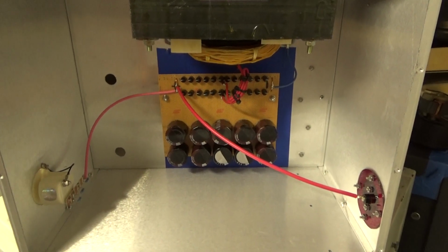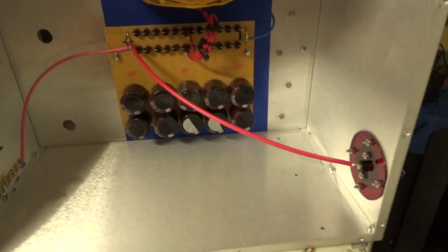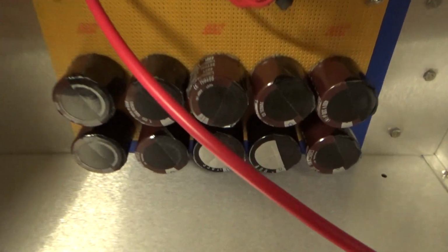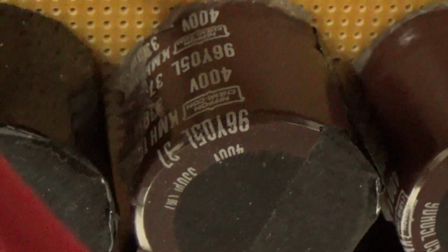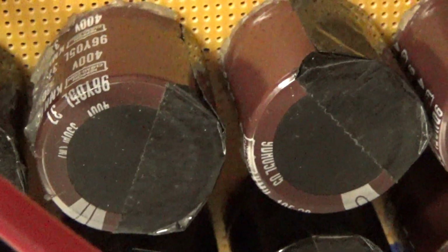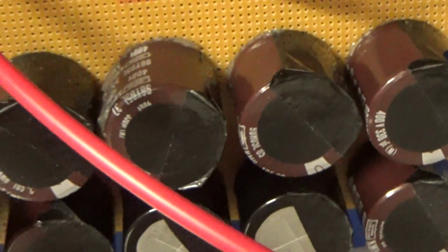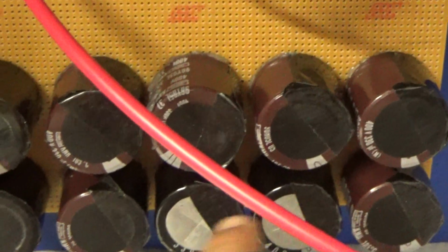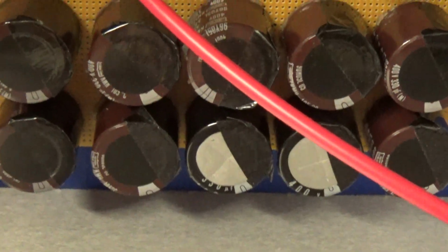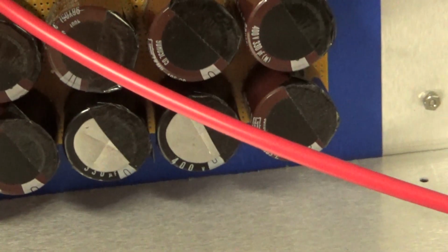First off, you have 10 capacitors in here. As you can see, they have a voltage rating of 400 volts. If you take 400 times 10, since they're all in series, you come up with 4,000 volts. For some reason they have silicone all on the sides, and electrical tape on half of them. Two are black, the rest are brown. So those will be coming out.